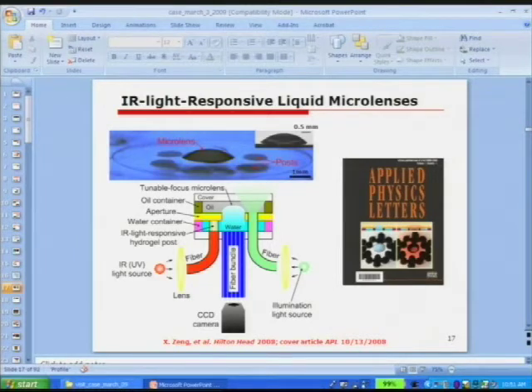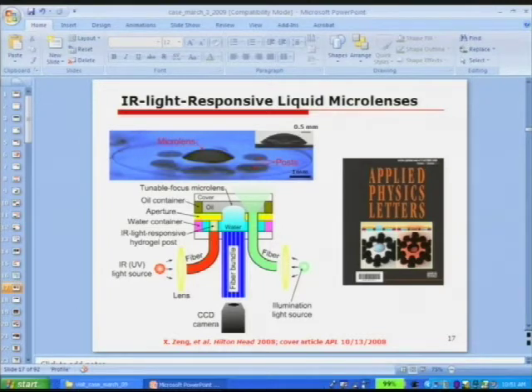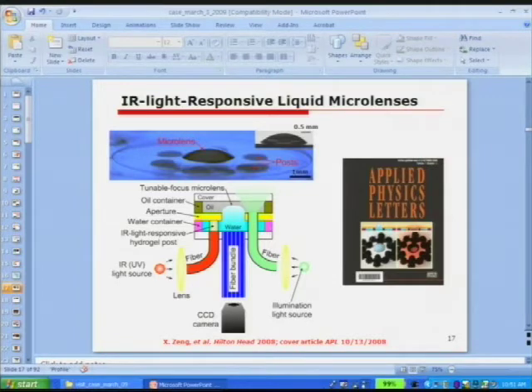Next we want to make this into a medical instrument — the endoscope prototype. Basically, we have a fiber bundle at the center for image acquisition. We have one set of fibers to activate the hydrogels — which requires light-responsive hydrogels, specifically infrared light-responsive hydrogels — and another set of fibers for illumination. Everything is bundled into a chunk of fiber bundle, with the tunable lens at the distal tip. This work was published in APL.